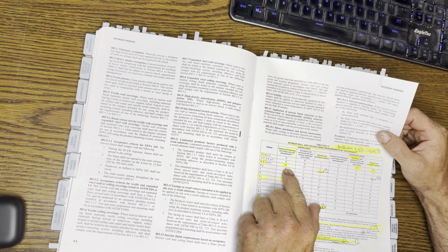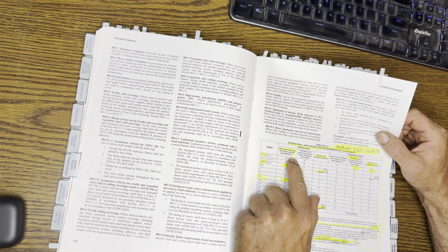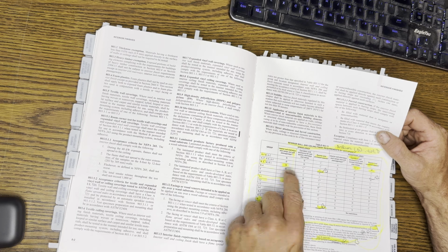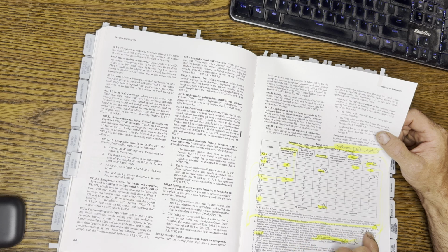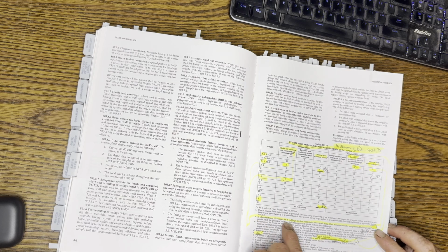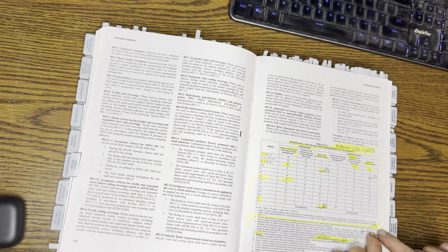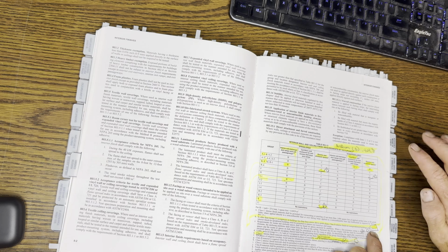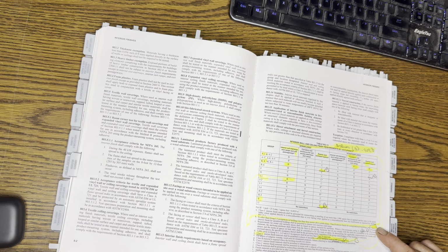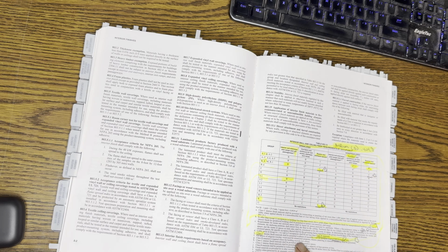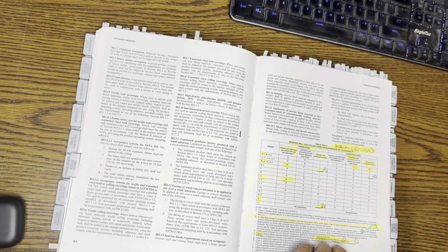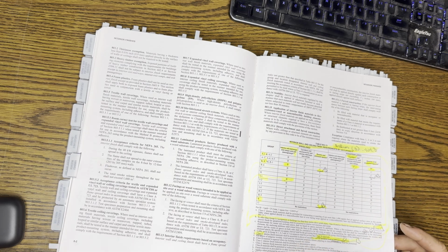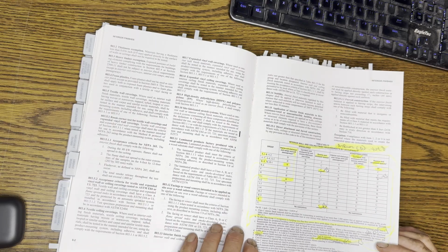Let's take a B occupancy. So the interior exit stairways, I have to have a Class B interior finish. But let's see, if I go down here... Yep, so Class B interior, see, so I can get away with Class C in many cases here if I'm suppressed. So you look at these tables and then look at the footnote references, and then you can come down here and you can actually derate it. And in some cases, you could completely eliminate the requirements. You can go with the Class C is what I'm saying. You can't go above a Class C. You can't go above a 200 flame spread index for interior finish for occupiable structures, period. You're not allowed to.